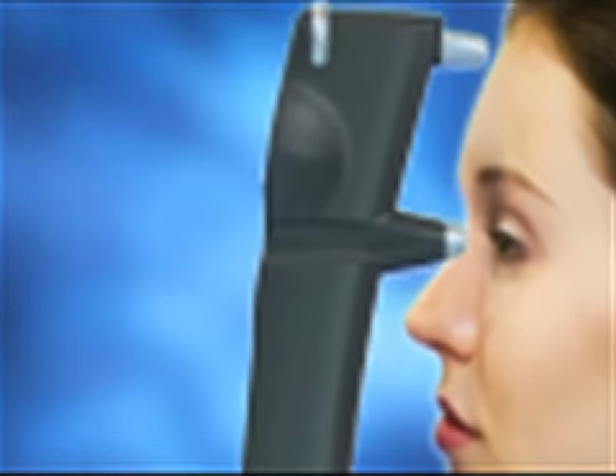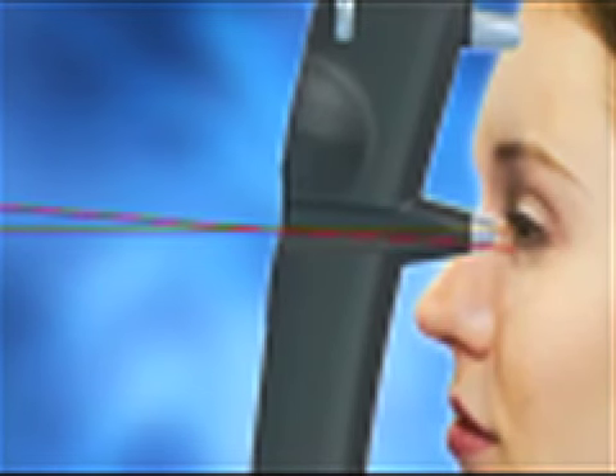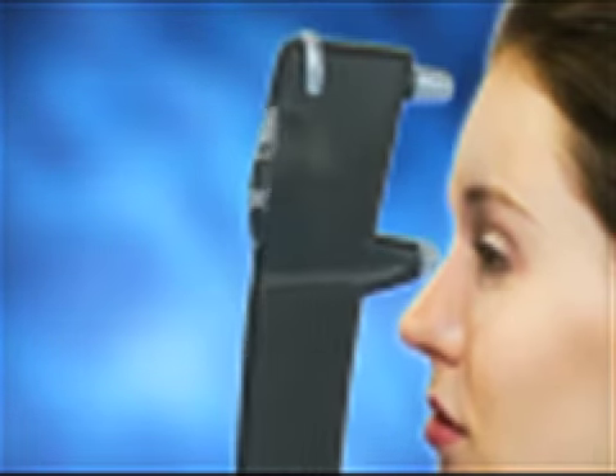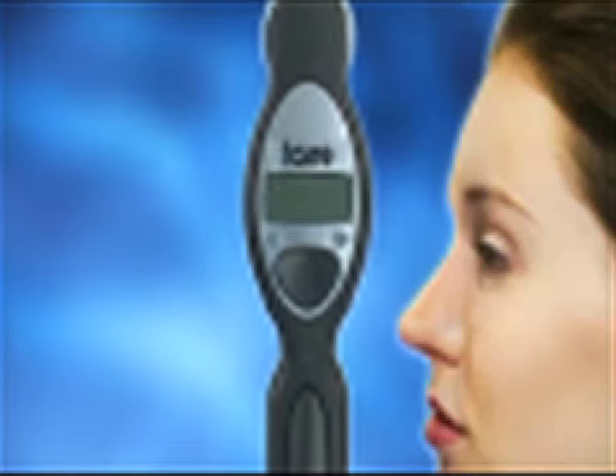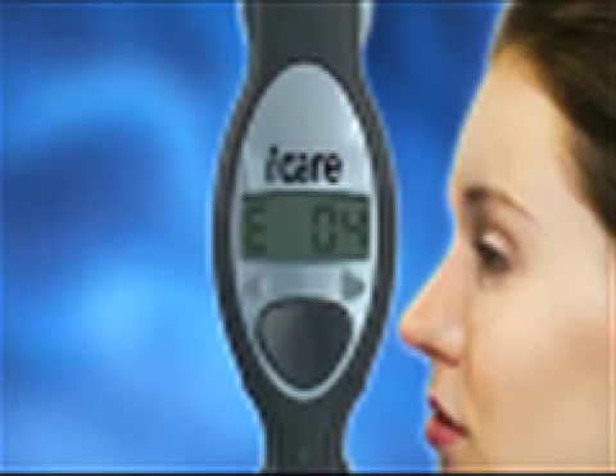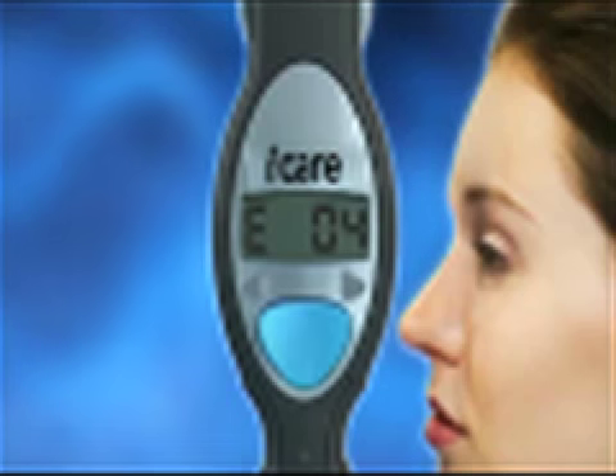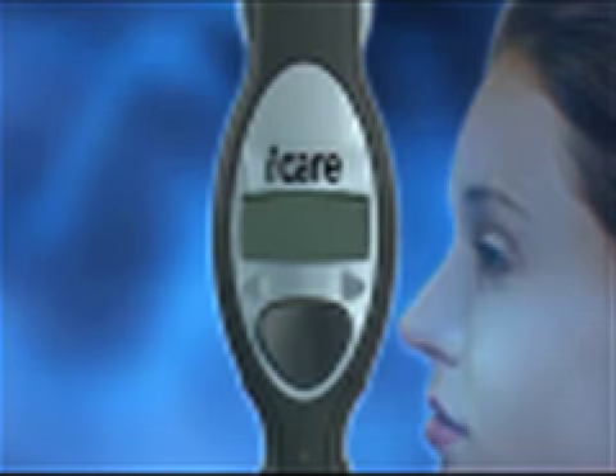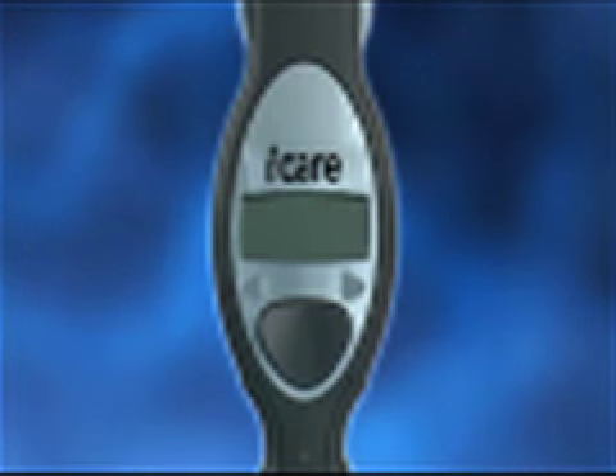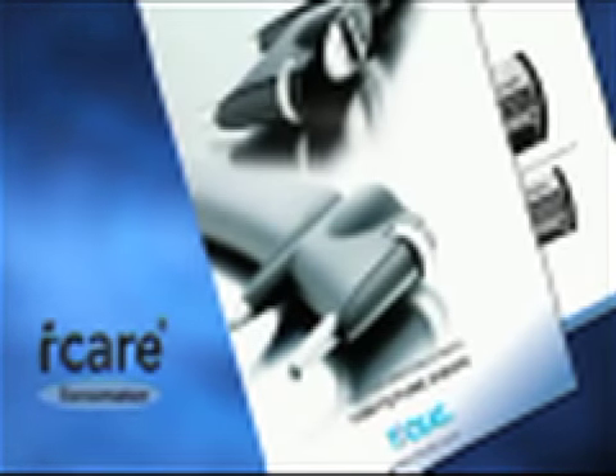If the groove is not in a horizontal position and the tonometer is pointing downwards, the probe may move too fast, producing an inaccurate measurement. This error will be indicated by an E04 reading on the display. Clear the error message by pressing the selector button once. The measurement can now be repeated. For other error message indications, please read the printed user's and maintenance manual carefully.